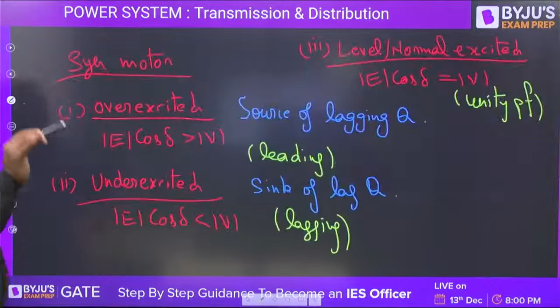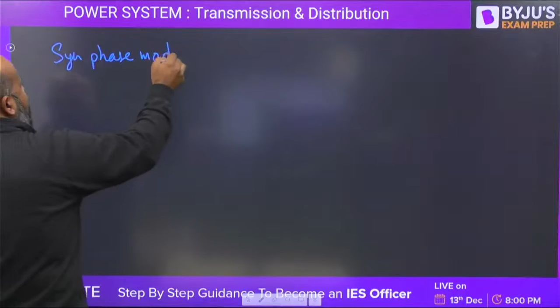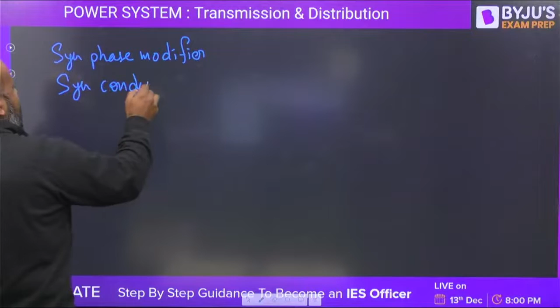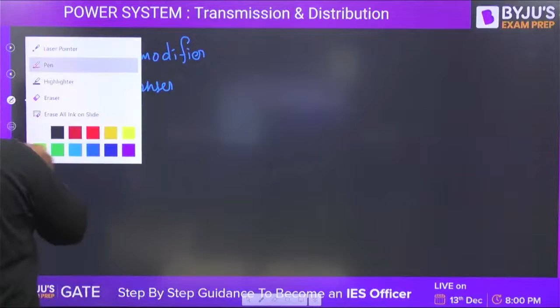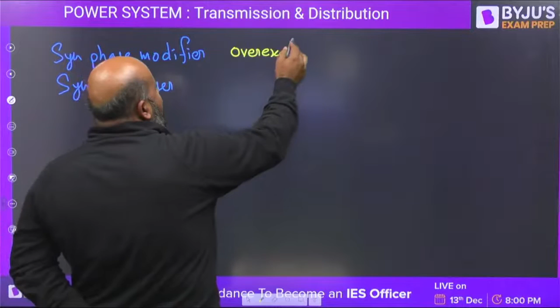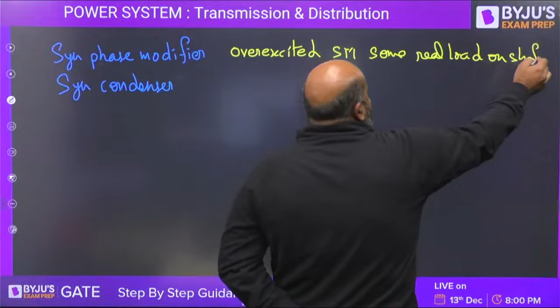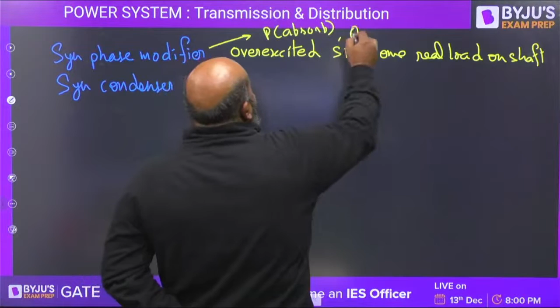First, you understand what is the difference between a synchronous condenser and synchronous phase modifier. Synchronous phase modifier and synchronous condenser. What is the difference? In one line I will give you the difference, and more than that is not required. It is an overexcited synchronous motor having some real load on shaft. What does it mean? It means it absorbs real power from the supply and it supplies lagging reactive power to the system.